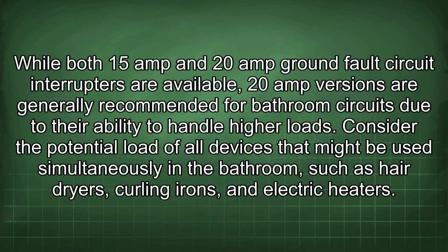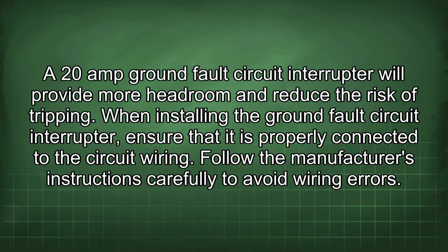While both 15 amp and 20 amp ground fault circuit interrupters are available, 20 amp versions are generally recommended for bathroom circuits due to their ability to handle higher loads. Consider the potential load of all devices that might be used simultaneously in the bathroom, such as hairdryers, curling irons, and electric heaters. A 20 amp ground fault circuit interrupter will provide more headroom and reduce the risk of tripping.